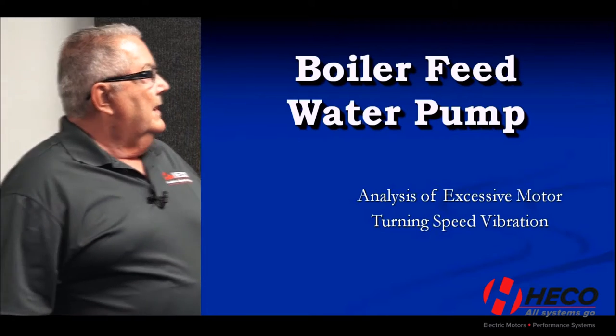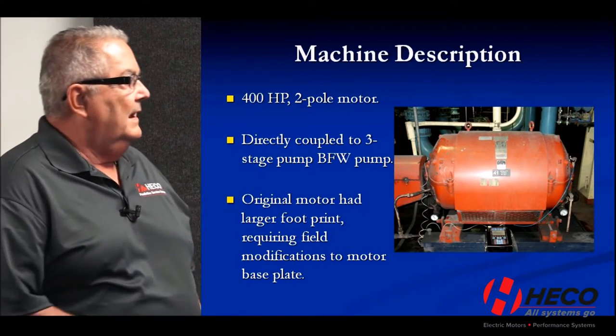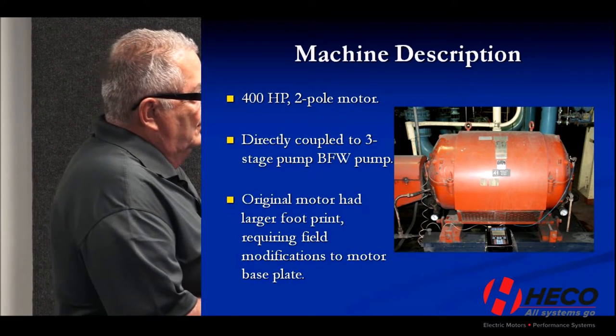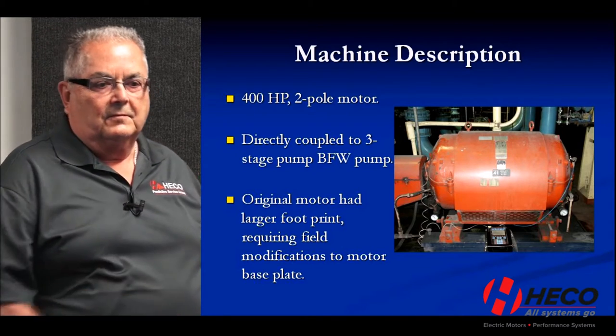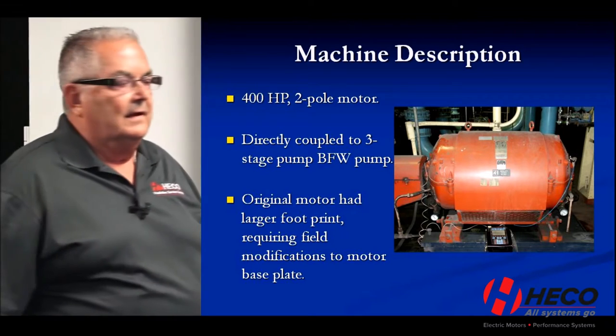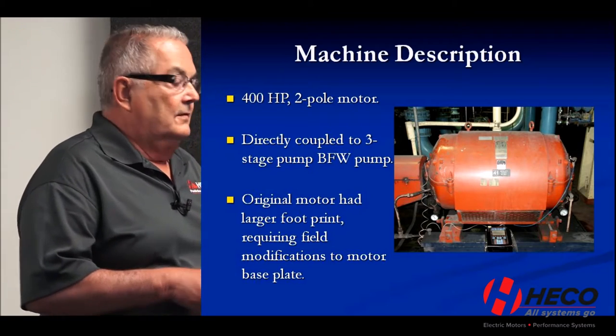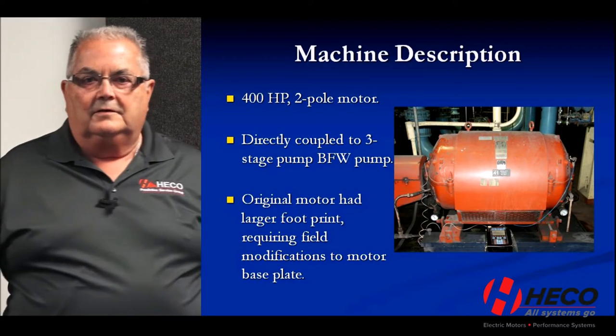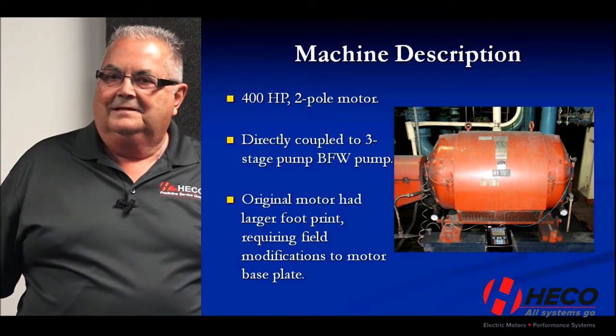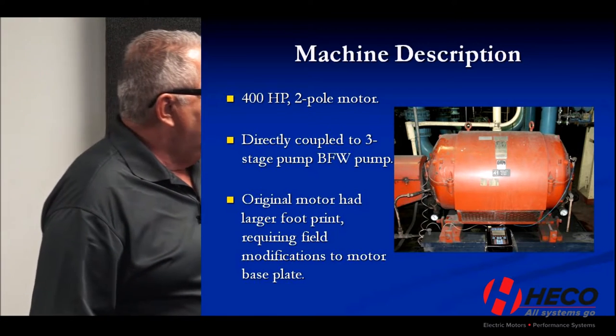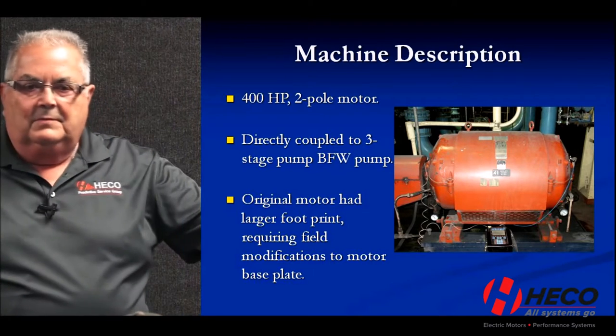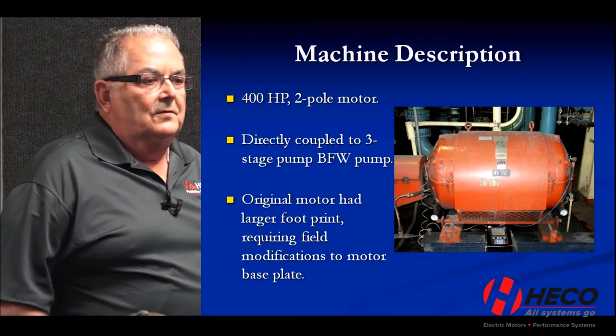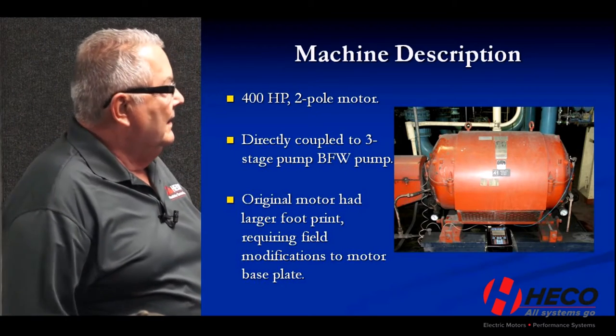Next we're going to look at a boiler feed water pump that had excessive vibration at its turning speed. It's a much smaller pump — the motor is coupled directly to the boiler feed water pump. It's a two-pole motor running nominally at 3,600 RPM. This is a new installation of a used motor. The previous motor had a problem, they didn't have a spare, so they went out and bought a used motor. It had a larger footprint — the span between the anchor bolts was longer — so they had to do some modifications to the base plate in order to install this motor.